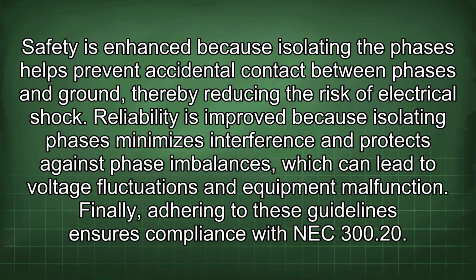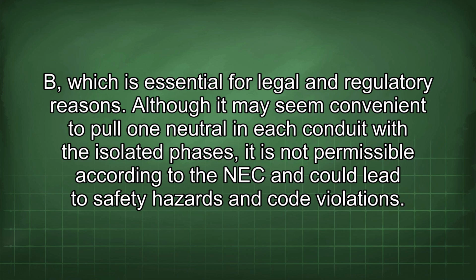Safety is enhanced because isolating the phases helps prevent accidental contact between phases and ground, thereby reducing the risk of electrical shock. Reliability is improved because isolating phases minimizes interference and protects against phase imbalances, which can lead to voltage fluctuations and equipment malfunction. Finally, adhering to these guidelines ensures compliance with NEC 300.20(B), which is essential for legal and regulatory reasons.